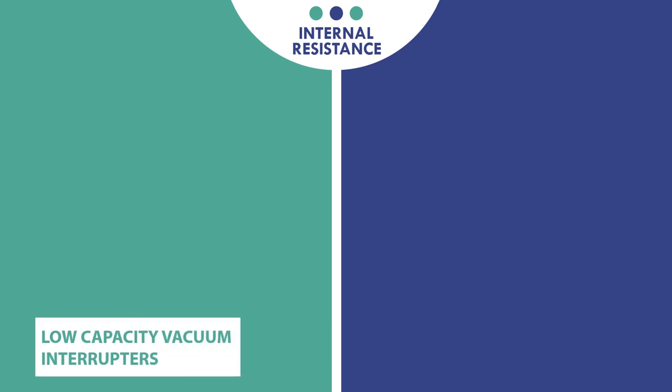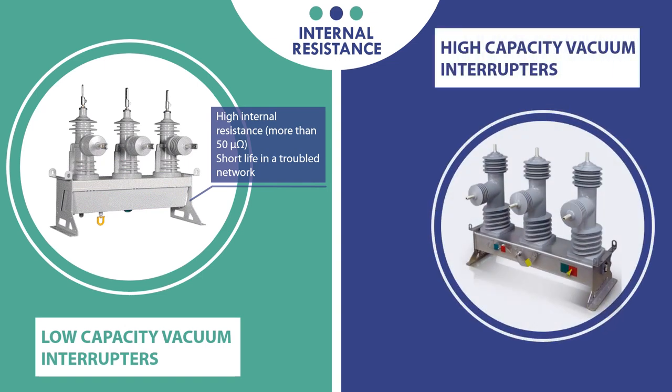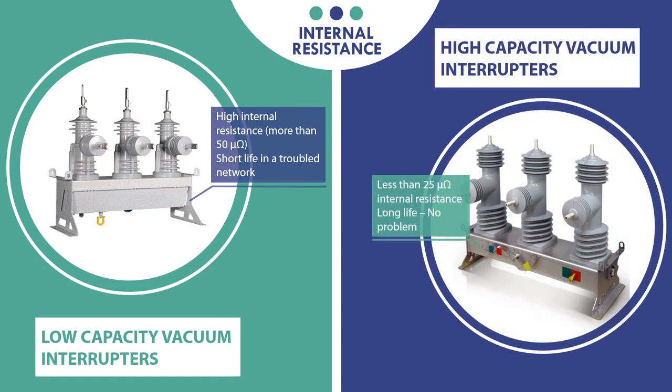Moving to the fourth important factor when choosing a right recloser: internal resistance. Here we have low capacity vacuum interrupters, which are generally characterized with high internal resistance more than 50 micro ohm and low short circuit capacity. It also has a short life in a troubled network, which makes life cycle cost quite high. Another type is high capacity vacuum interrupters. Their strong point is that it has less than 25 micro ohm internal resistance and can take high level of short circuit current. It has a long operating life, which gives it a low life cycle cost.